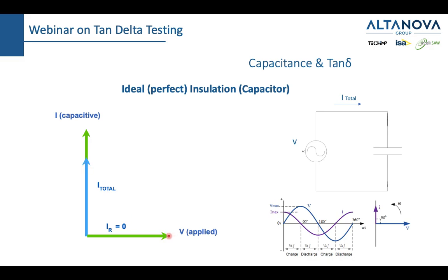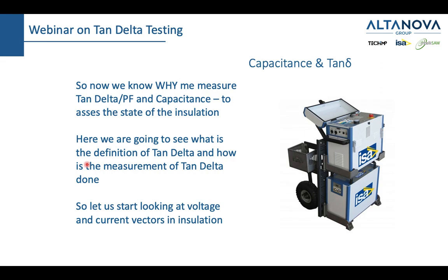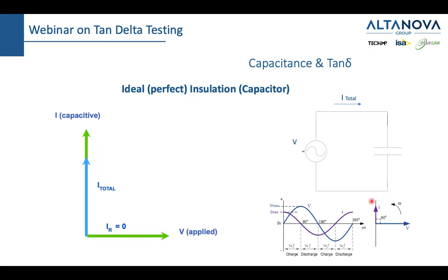By the way, tan delta test is an offline test. I didn't mention it before, but you cannot do a tan delta test while the asset is being used. What you can do, if you want to continuously measure tan delta, is install sensors, and then you will have online monitoring of tan delta, which is different. Again, you're measuring the same thing, but today we're talking about offline testing. So that means my testing equipment will apply a voltage, and then it will measure current. And this is one of the testing equipment which we use. Later you will see some others. This would be an STS-5000, and this would be the TD-5000, which will apply up to 12 kilovolts.